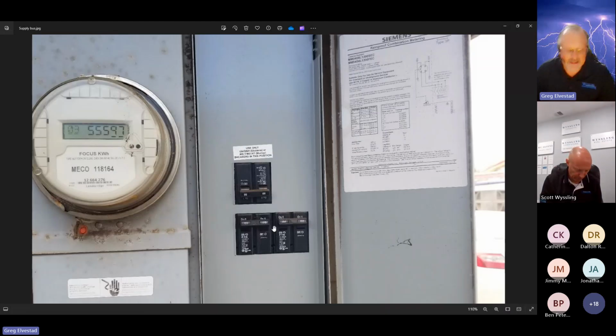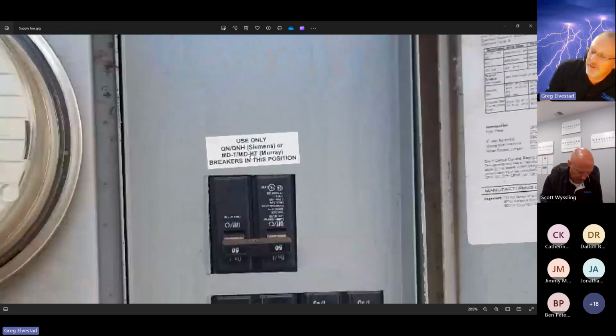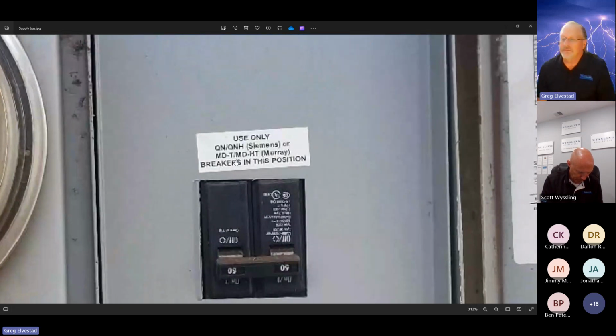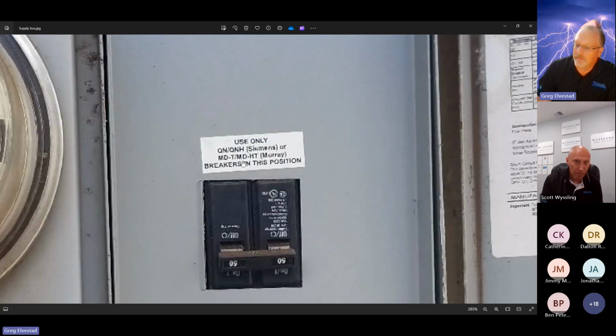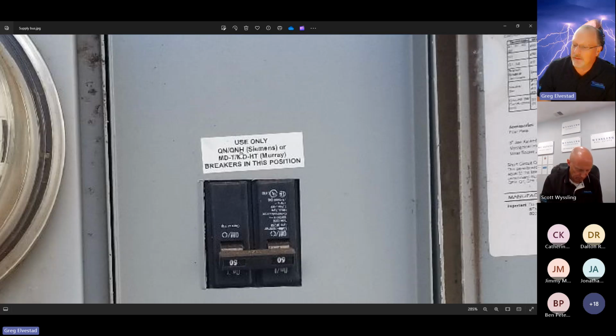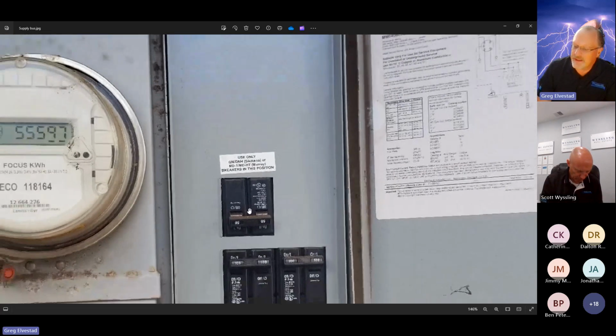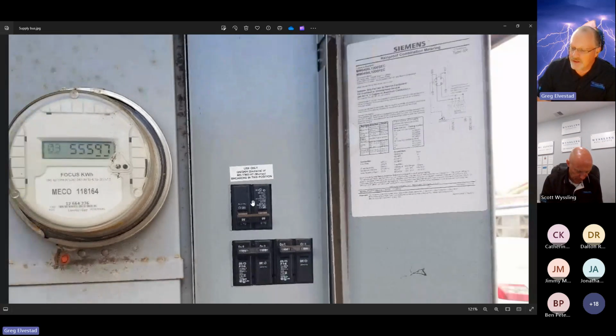Now, this one here is an example of a code violation. So make note of this. The breaker handle is upside down. That's not permitted anywhere in the country because that was a violation since about 1973. But the other thing you want to be careful about is looking at this label right here. Use only this type of breaker. Well, this model breaker, you can check that later, physically takes this entire 6-inch space right here.